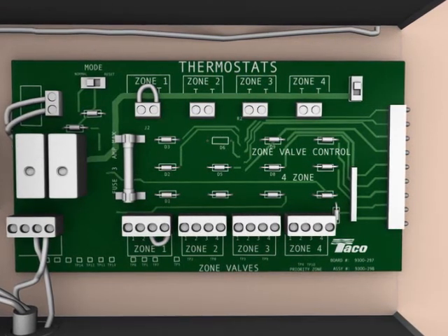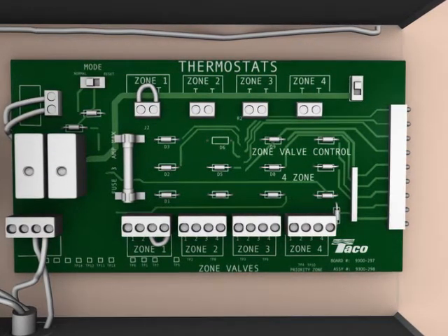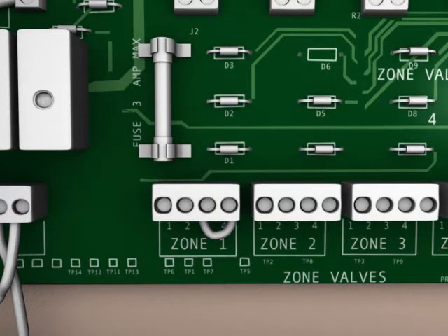If the furnace is equipped with air conditioning, the Radiant Link system must be interlocked with the air conditioning so that it can't operate when the air conditioning is on. Remove the jumper wire from between Zone 1 terminals 3 and 4 and provide an interlock to the air conditioning controls to break the connection between terminals 3 and 4 when the air conditioning operates.